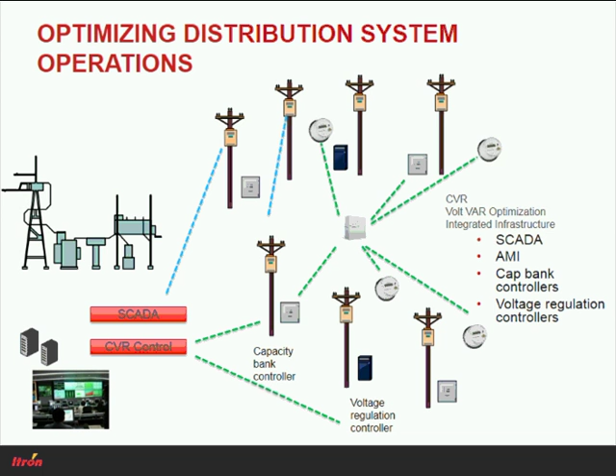When you begin to use AMI and SCADA in combination, what you can get is conservation voltage control systems. You can get volt-var optimization, where you're actually using capacitor bank controllers and voltage regulation controllers to control operations within the grid. So there are some tools that exist out there, but we haven't necessarily been using them in the way that can best help us.